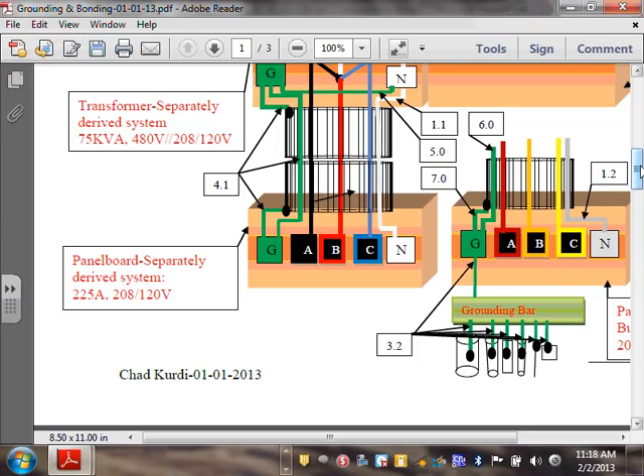But here's an alternative for you though. Here's a solution for this. The solution would be to feed the building from a different service. If it's a bigger building, you can have a different service coming to it, like you come from the termination box, go to the CT cabinet and tap it. That will solve the problem. Because the hazard, guys, from bonding here is more than from not bonding. There's hazard from bonding and not bonding. If you bond the neutral here, you create more hazard than not bonding it. Okay, so that's where we bond them.